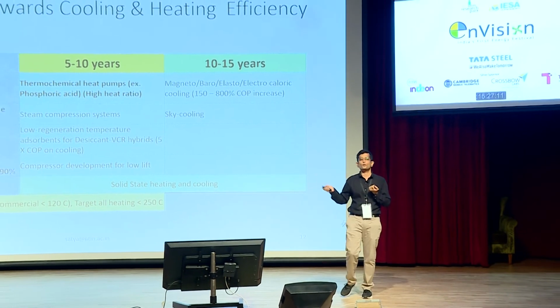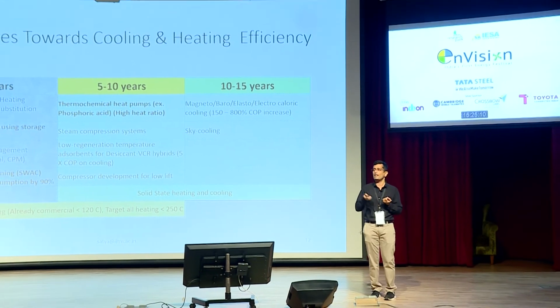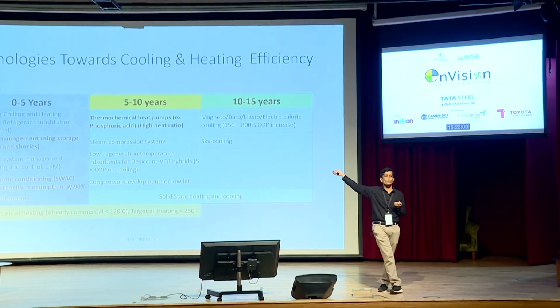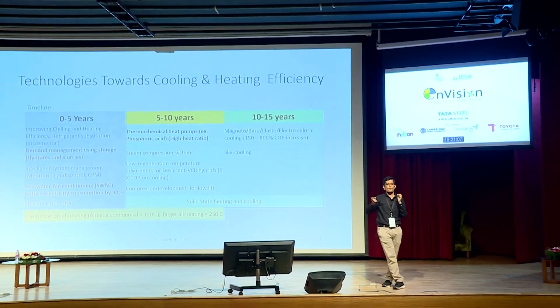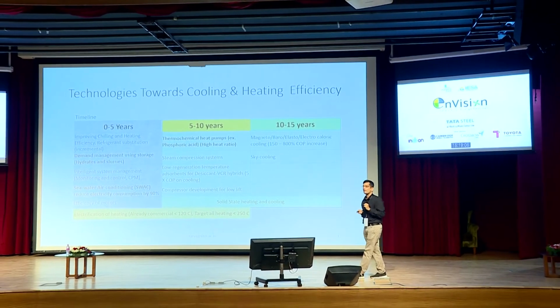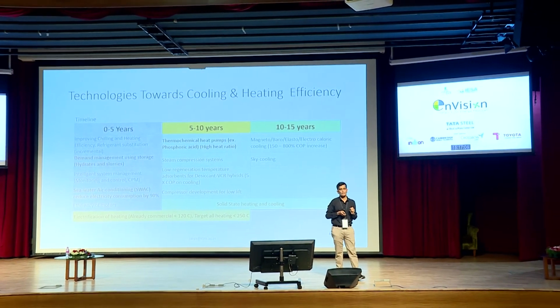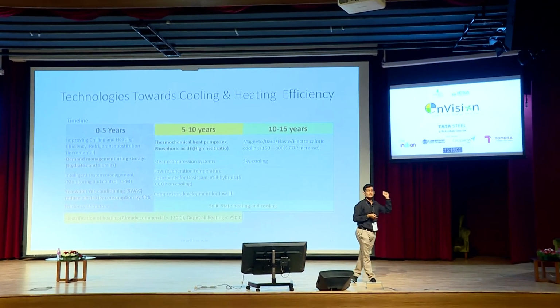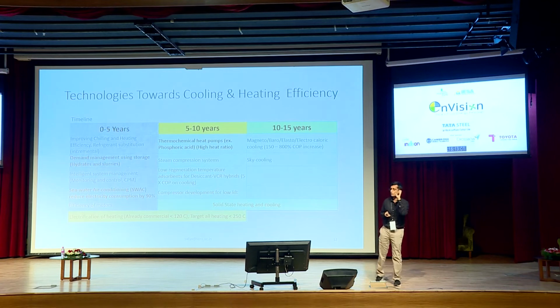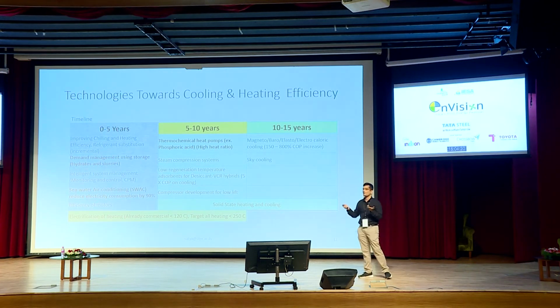I'll tell you why this is so exciting. I can take heat available in a cooling tower as low as 30 degrees C, and with very little electricity input, boost it up to 90 degrees C. Whereas with vapor compression refrigeration, I'd need a compressor to put in the energy, phosphoric acid can do that with very little pumping power. But why can't I use it right now? There are some material challenges, but that's going to be exciting.